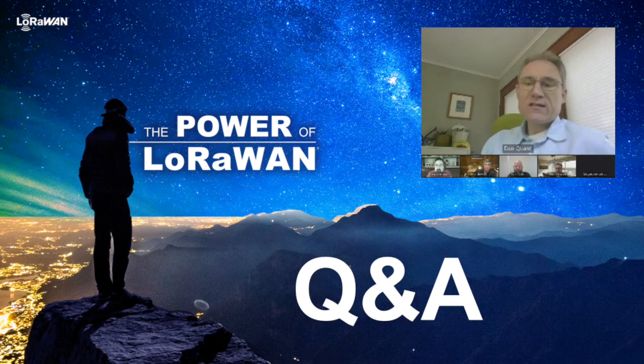And this is where the disconnect comes in. We're collecting data off of sensors that are often battery powered in awkward to reach places, limited to maybe no more than 11 bytes in the US. And how do we now integrate that data into a backend that's expecting to see Modbus, OPC UA, or BACnet? So where do you now do that conversion?